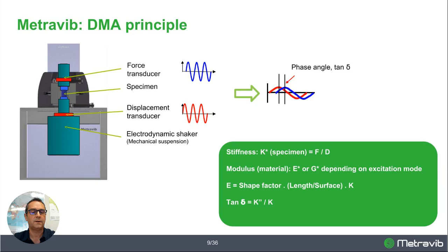So the key specification and parameters for the DMA testing are a lot, in fact, and all of them are critical. And so the first one, and probably the most important, is the mechanical design, because we are measuring with the DMA the stiffness of a specimen, and this stiffness has to be quite low compared to the stiffness of the mechanical test frame. That's the first very important condition. So the stiffness of the frame is a specific key feature, and you will see how we deal with this with the DMA+ series.